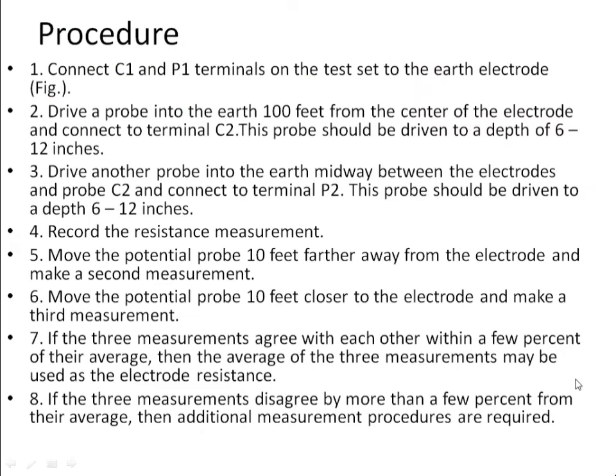Let us see the procedure. Connect the C1 and P1 terminals on the test set to the earth electrode as shown in the figure. Drive a probe into the earth 100 feet from the center of the electrode and connect it to terminal C2. This probe should be driven to a depth of 6 to 12 inches into the ground. Drive another probe into the earth midway between the electrode and probe C2 and connect it to terminal P2. This probe should be driven to a depth of 6 to 12 inches. Record the resistance measurement. Move the potential probe 10 feet farther away from the electrode and make a second measurement. Move the potential probe 10 feet closer to the electrode and make a third measurement.